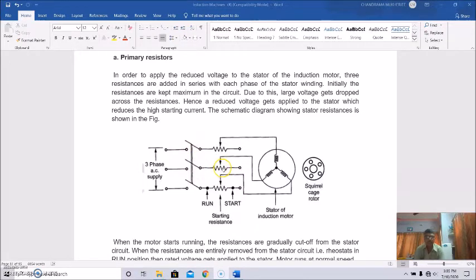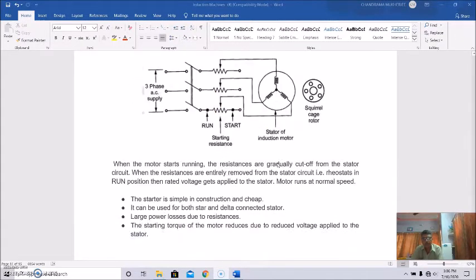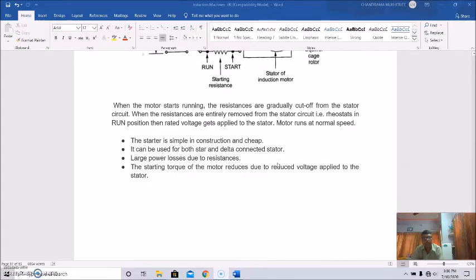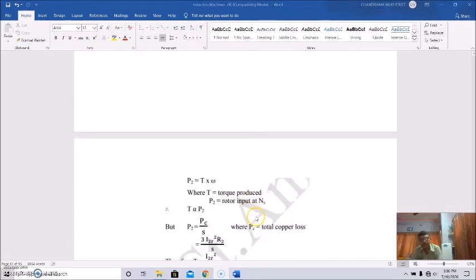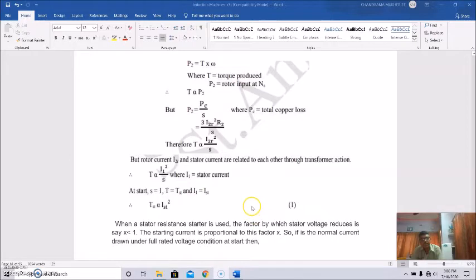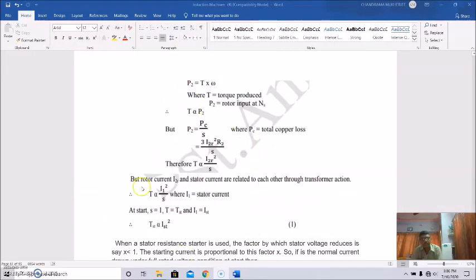across the stator winding, and the motor will run at the rated voltage, and when it is loaded, the full load or rated current will flow. The main advantage of this starter is that it is simple in construction and cheap, and it can be used with both star and delta connected stators. Large power losses due to the resistance happen here. The starting torque of the motor is reduced due to the reduced voltage applied to the stator, and this can be discussed mathematically here.